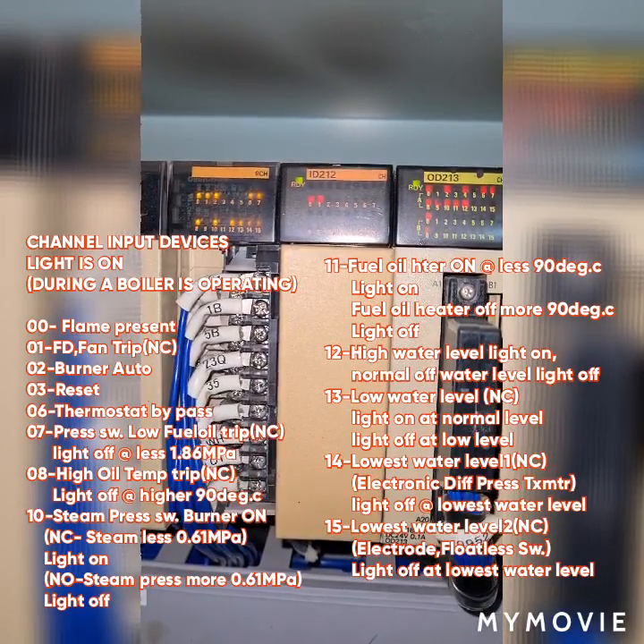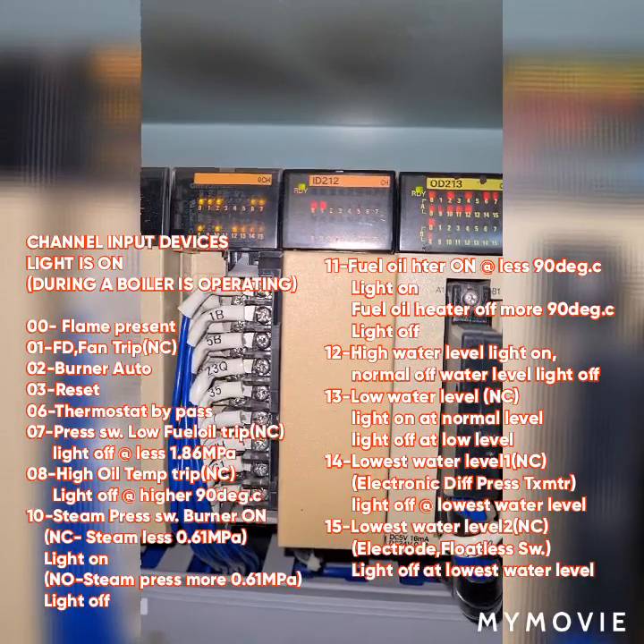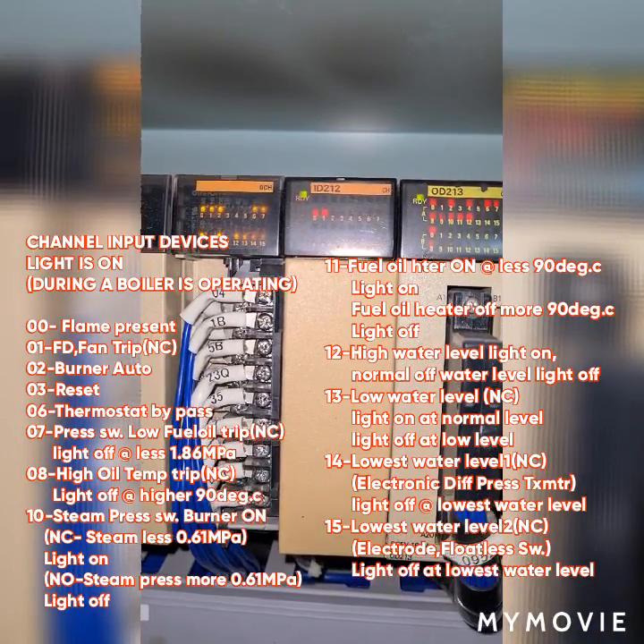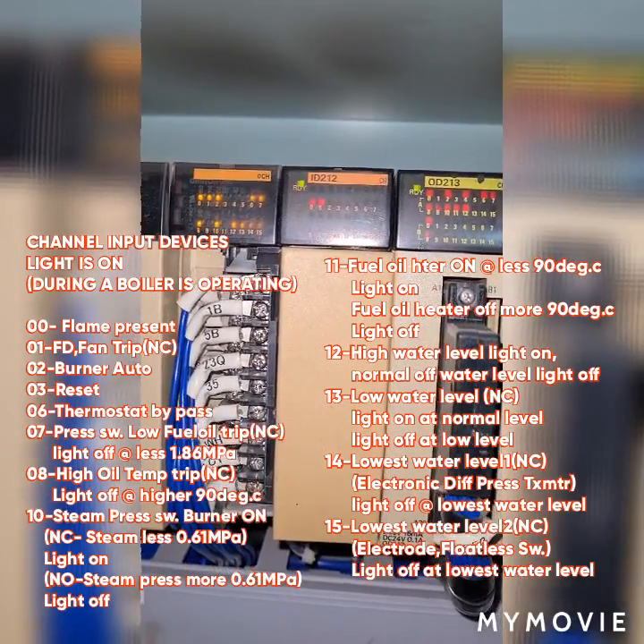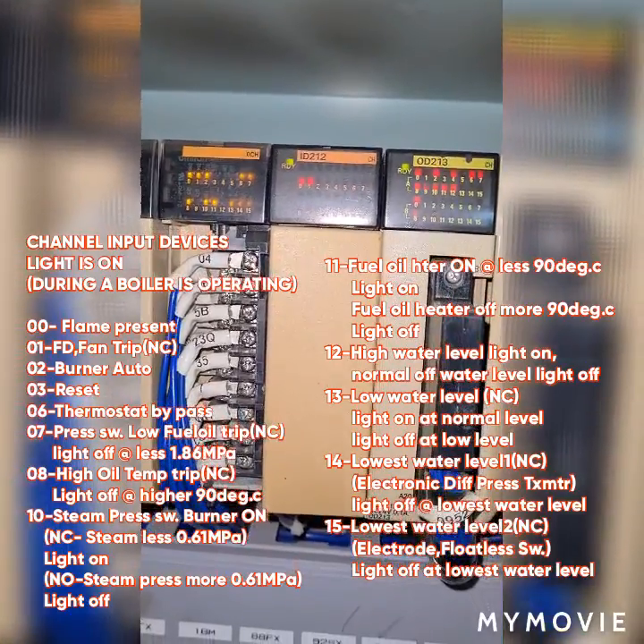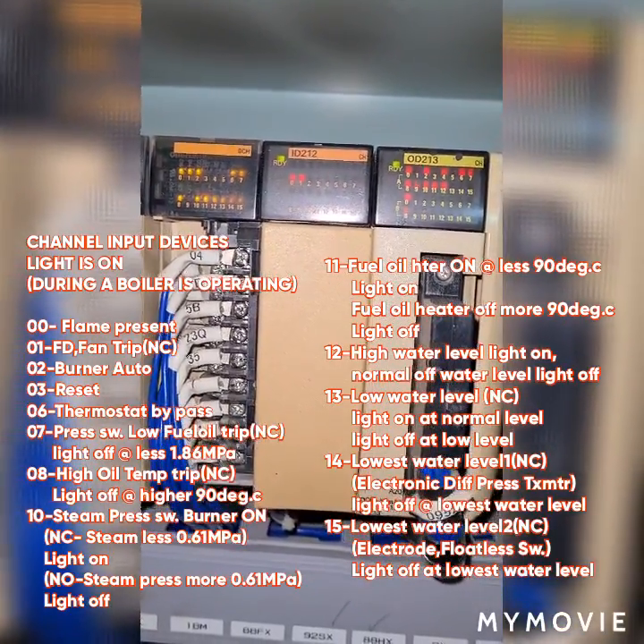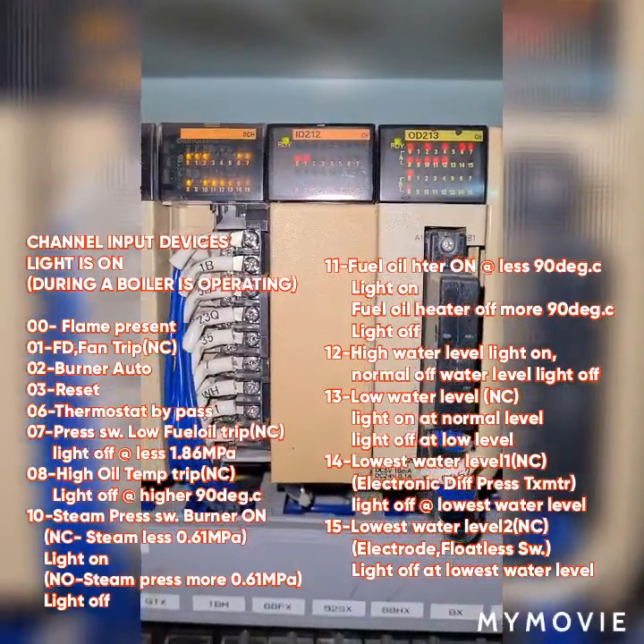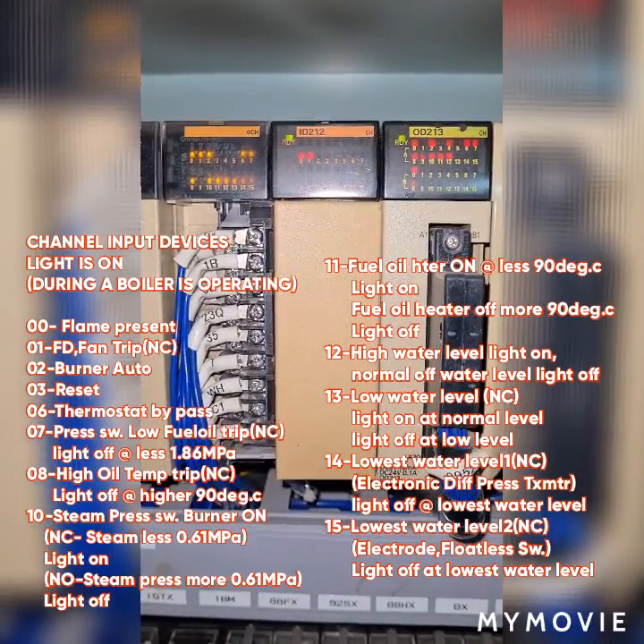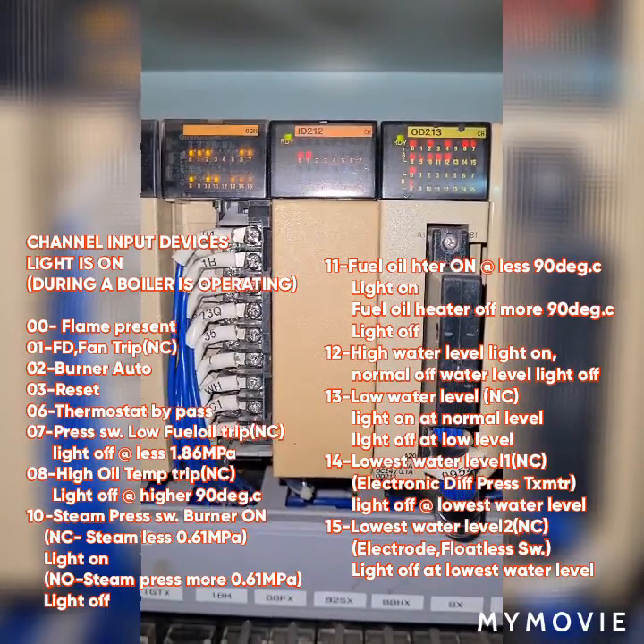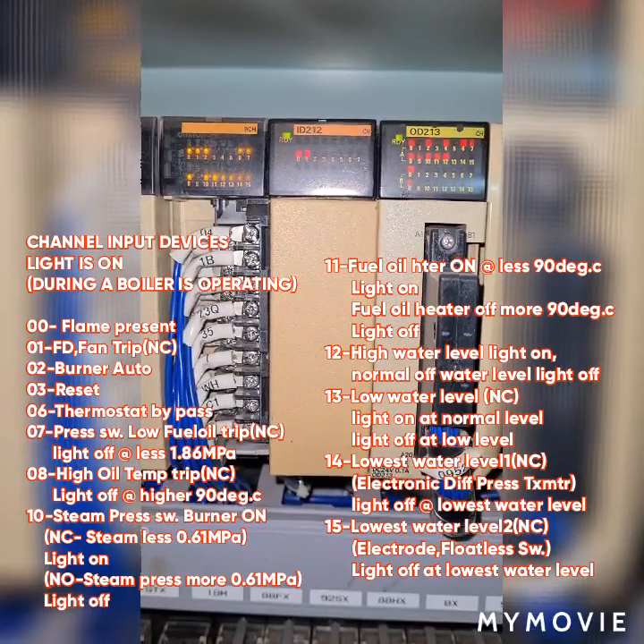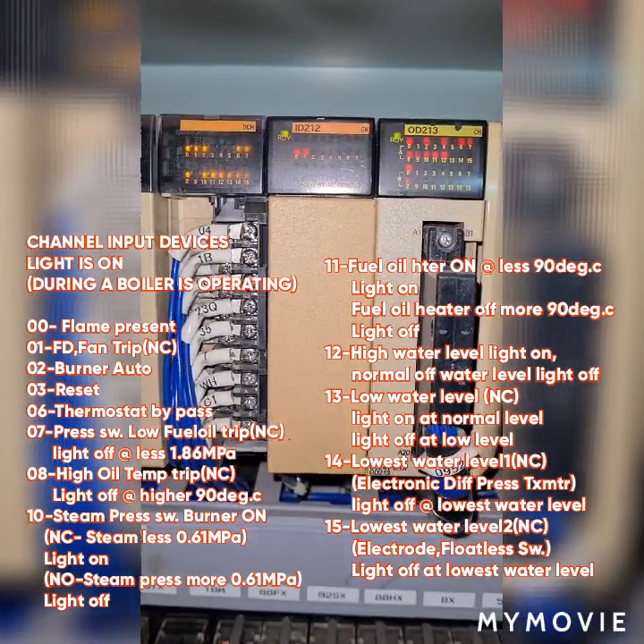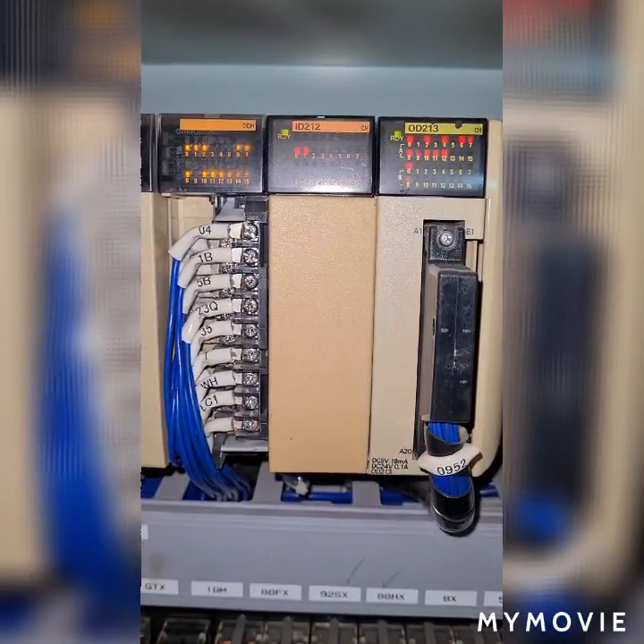00 channel means flame present, 01 for forced draft fan, 02 for burner auto, 03 for reset, 06 for thermostat bypass, 07 for pressure switch low fuel trip, 08 for high oil temperature trip, 10 for steam pressure switch burner on, 11 for fuel oil heater on, 12 for high water level on, 13 low water level on, 14 lowest water level on, and 15 for lowest water level on.